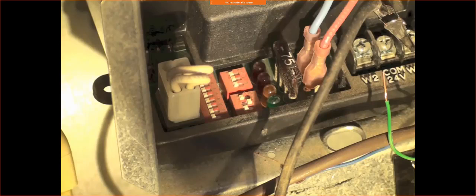What that does is it helps the electrical board know that the inducer motor is running. The board is dumb, okay? It's plain and simple. It only understands electricity going out and electricity coming in. It doesn't know that the inducer motor is running, okay? It knows that it sends a signal to the inducer motor to turn on. There's no high-tech finagled way on this equipment for there to be a signal sent back to the board.